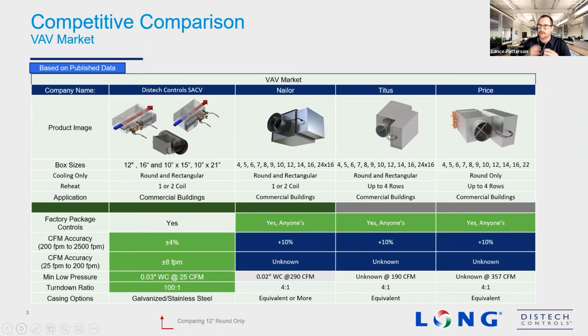Because of that 4-to-1 turndown ratio, the traditional VAV really needs a variety of different sizes. You can see there 4-inch all the way up to 16-inch, and sometimes dual VAVs as well to achieve higher flows. When we look over at the SACV, it's really only 2 sizes, especially on the round side, and then 2 sizes on the rectangular side, because we're able to take a 12-inch VAV and still ramp up to 2000 CFM, but ramp all the way down to say 25 CFM. So we can achieve some incredible turndown, which allows us to have less SKUs, if you will, less product to have to choose from, which we'll explain some of those benefits in a couple of slides as well.